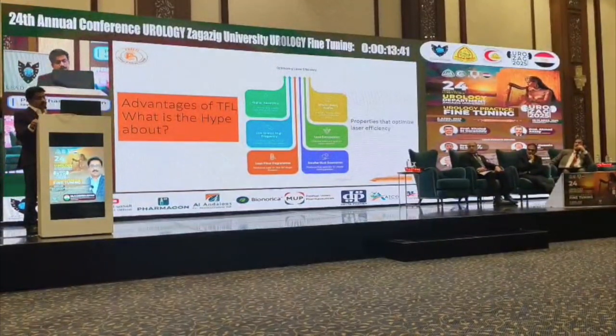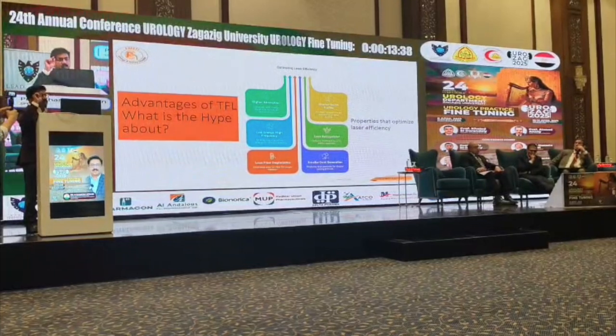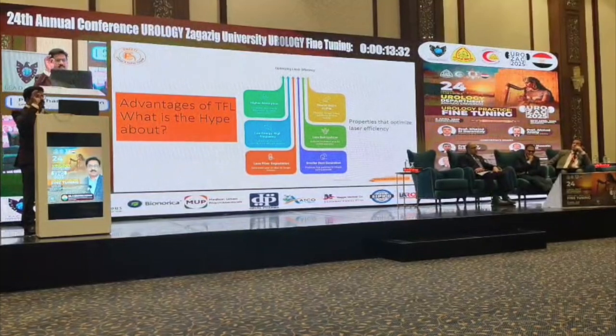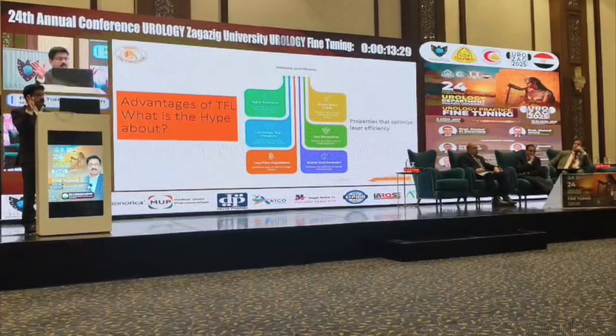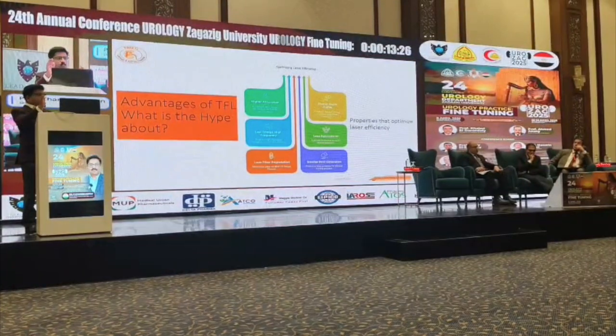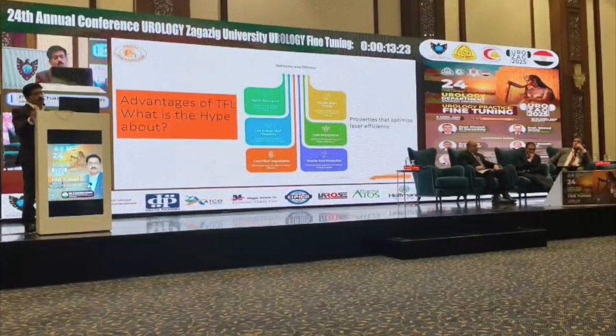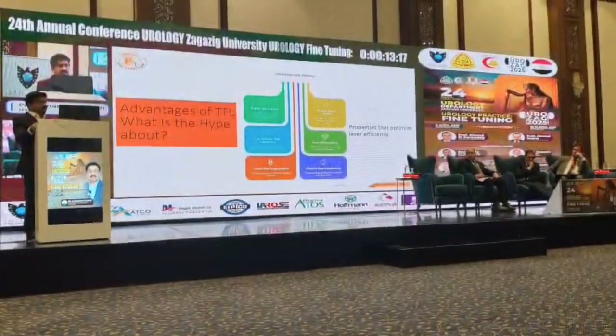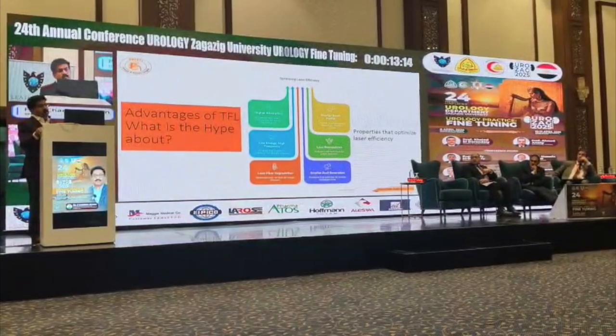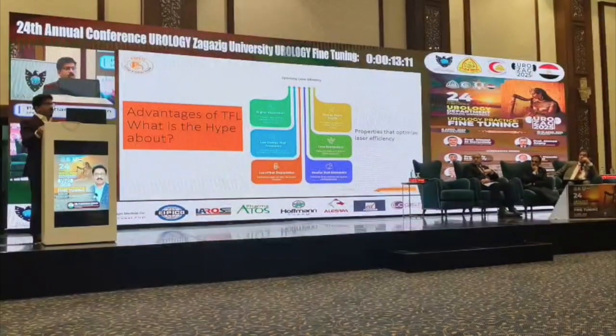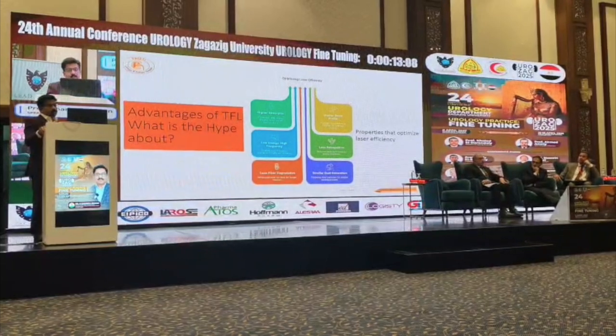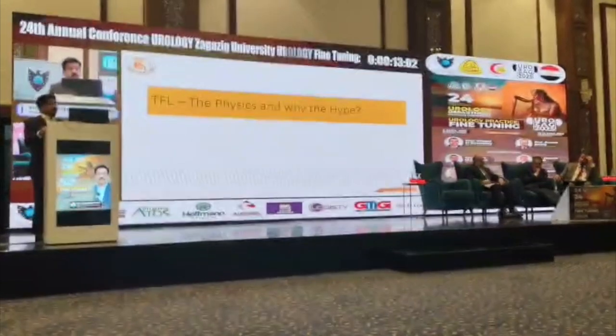You can change the energy settings. The degradation of the laser fiber is very, very less. The focused beam is there with no dispersion — the laser is focused the way you focus, with no side scattering. The beam is very, very parallel. Retropulsion is less, there is no doubt. Professor Kisar was sharing that the new machine has very, very low retropulsion. Smaller dust can be produced because of the high frequency.